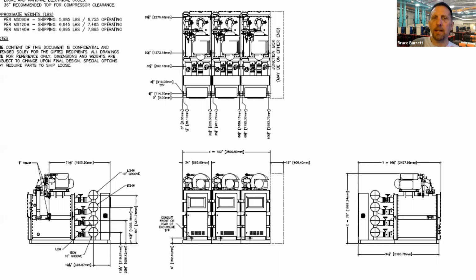Just a quick drawing of how they stack together in the mechanical room. From our factory, we do stub out the refrigerant vent piping out of the top of the machine. So bring them in, groove lock couplings together. We'll provide the single point power connection via conduit if you so choose. And very, very quick installation, compact footprint, 42-inch tube pull on these machines. 42 inches, that's an aisle width, and just about the requirement for high voltage clearance. So you can really stack a lot of these chillers in a small mechanical room and have them still easily maintainable.